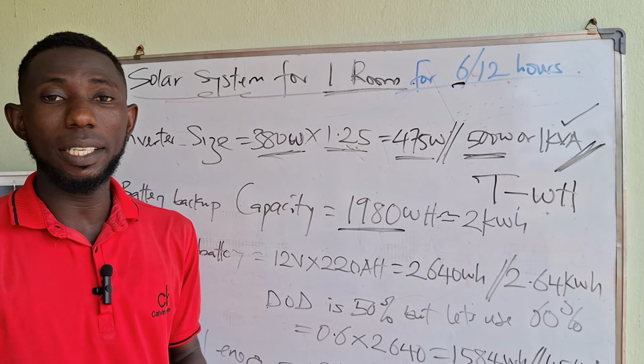50% DOD means that if you have a battery of full capacity, this is 1 to 100, then half is 50%. So from the manufacturer's design, you should not drain the battery below this point. You can drain from here up. When you get to this place, you have to shut down the system so that the battery will not overdrain. This is how the battery system is designed.